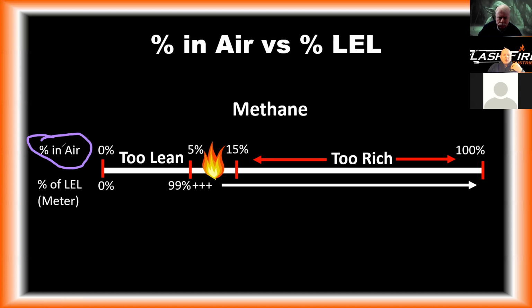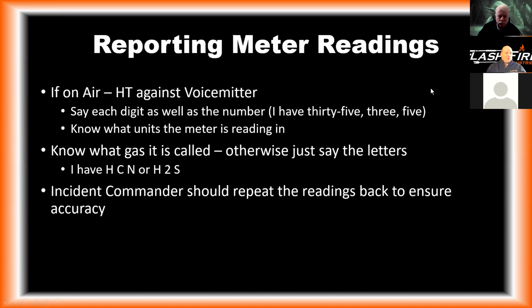So there are times where I'll go up to the guy and, before I knew this, say, hey, what do you got? And he'll say, I have 5%. Now, if I have 5% on my LEL meter, I'm like, okay, there's a good amount of gas there, but I'm not freaking out or anything like that. But what he was talking about was 5% in air. So he was actually at the lower explosive limit. So when you're talking with utility company personnel, make sure that you're specifying, are you reading percent in air or are you reading percent LEL? That would be very important.